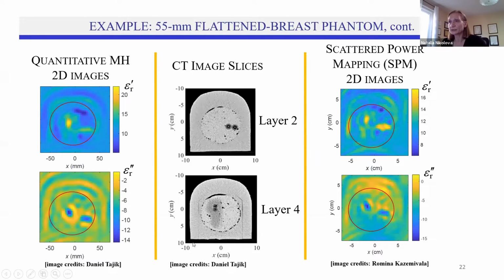We took the phantom to the medical school at McMaster, and there they imaged it with a medical CT scanner. This is an X-ray imaging device. It has very high resolution, higher even than magnetic resonance machines. And you can clearly see in those layers, second and fourth here, by the way, CT produces 3D images slice by slice. And of course, superb resolution, including the air bubbles that we couldn't drive out of our tissue mimicking substances. We cannot compete in terms of resolution with X-rays, but here are the microwave images that are reconstructed within milliseconds with quantitative microwave holography.